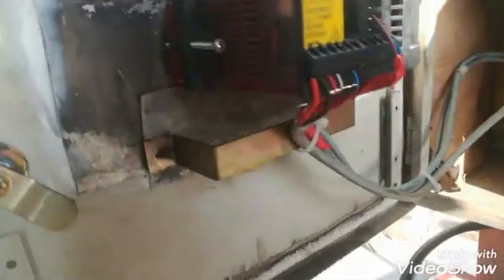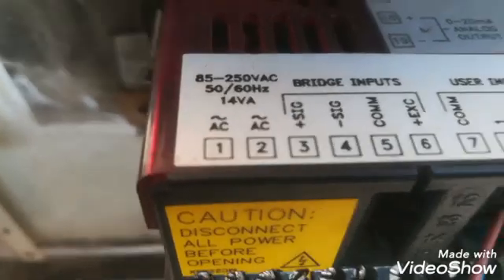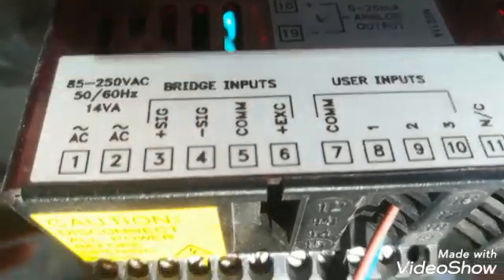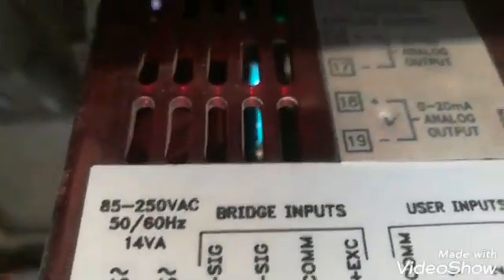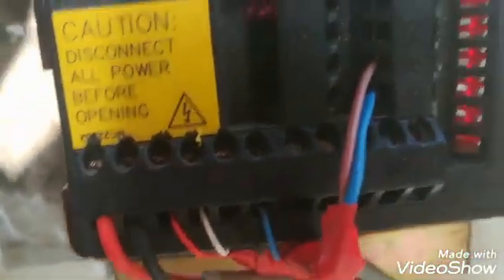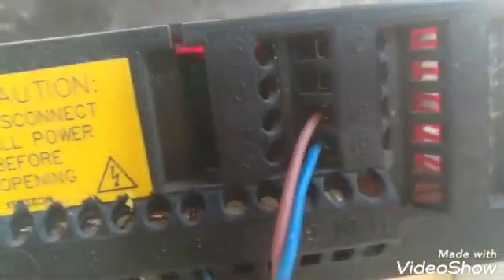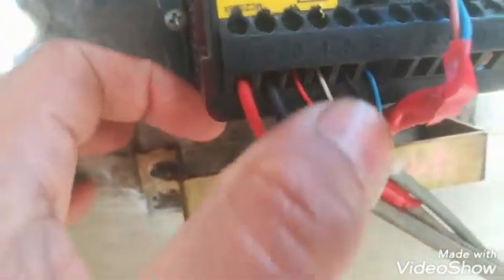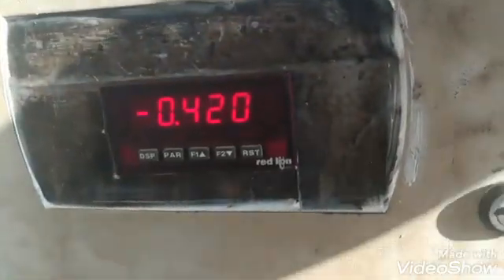First I will show you the connections of this Red Lion weighing indicator. Terminals 1 and 2 are for the AC supply. Terminals 3 and 4 are for the load cell signal, and 5 and 6 are for the load cell supply voltage. Terminals 18 and 19 are for the output milliamps. The brown and blue cable is for the output milliamps, red and black for the AC supply, and this is the load cell cable — a four-wire load cell connected to this weighing indicator.